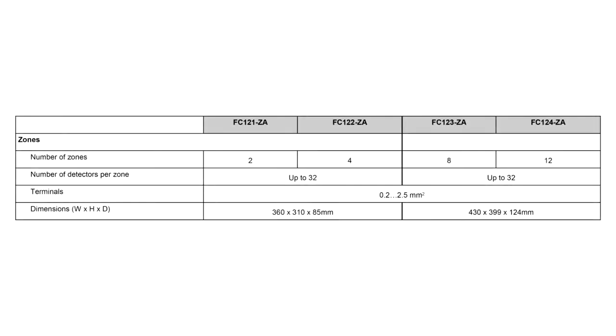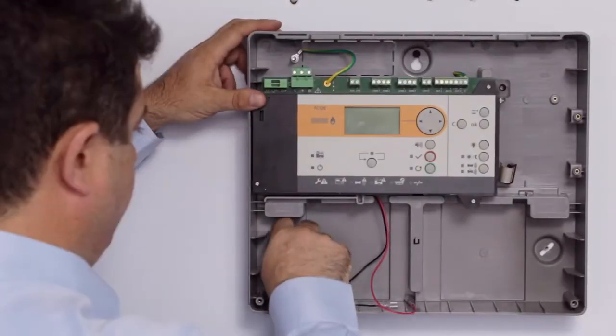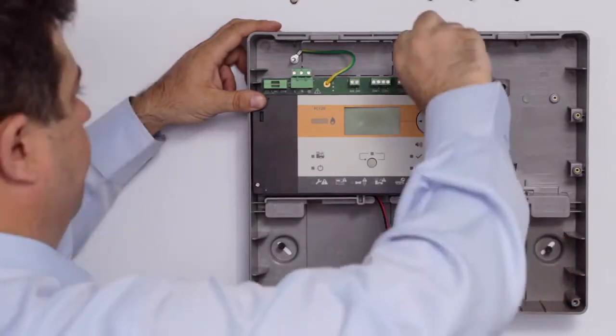We have 4 different types of panels, depending on the size of your project. You can select between 2 and up to 12 panel zones with a maximum of 32 detectors per line. Mounting the panel. Let us come back to the commissioning and mounting of the panel on the wall.